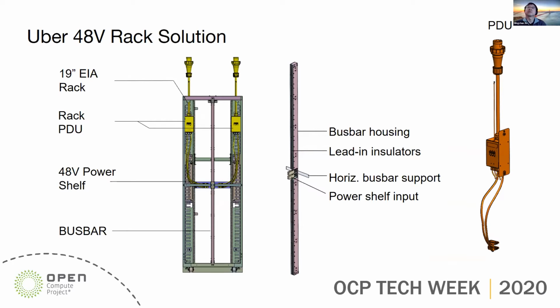This is the Uber 48-volt rack structure. Uber's rack is a 19-inch EIA rack. As just mentioned, we have the dual AC source. That dual AC source will lead into the rack through the PDUs. Each of the PDUs has two output connectors to supply power to the power shelf, and one AC plug. We follow the OCP standard 2.2 to design the rack bus bar to get the shelf power delivered to the servers in the rack.